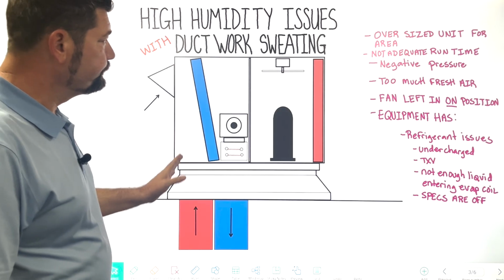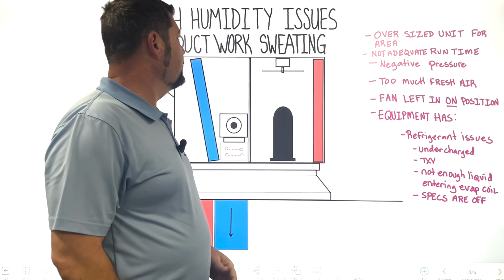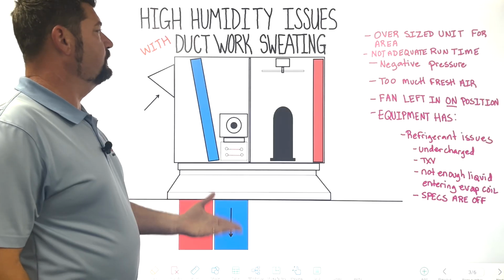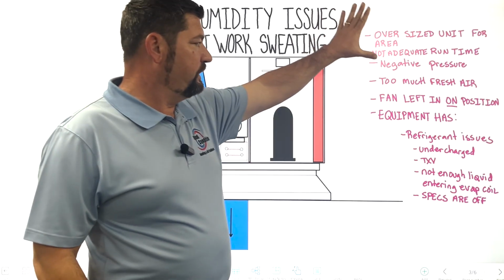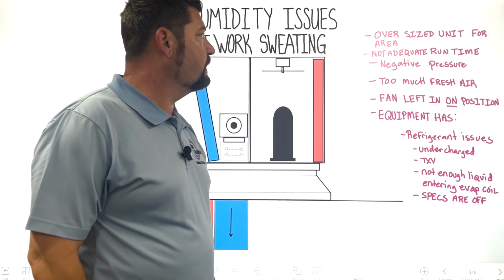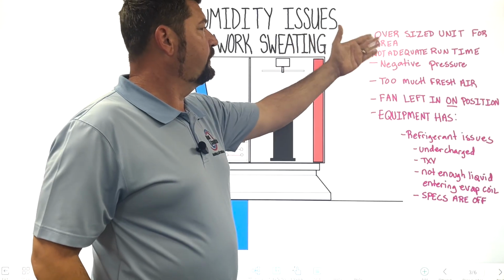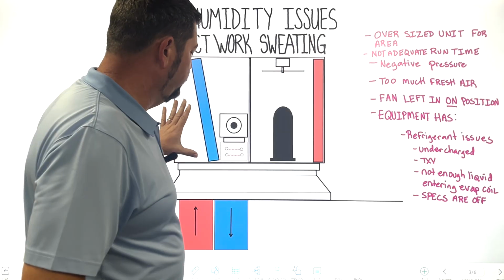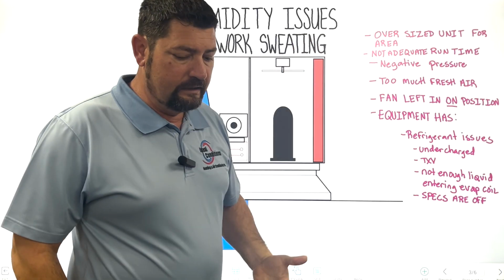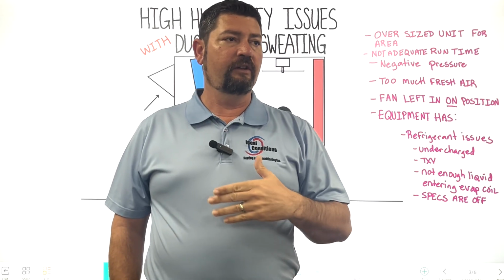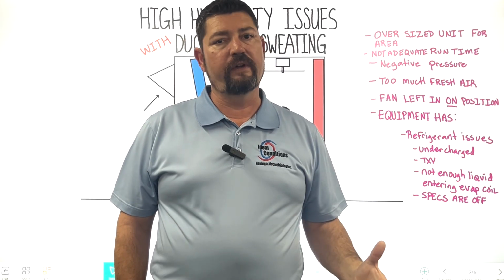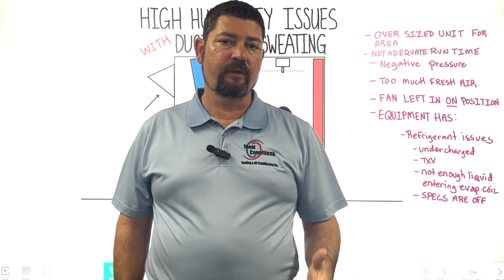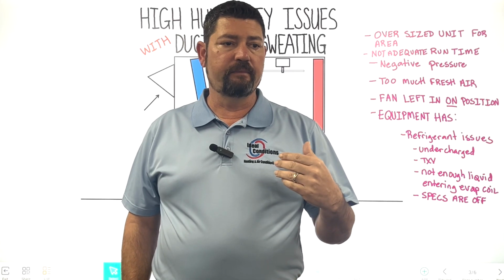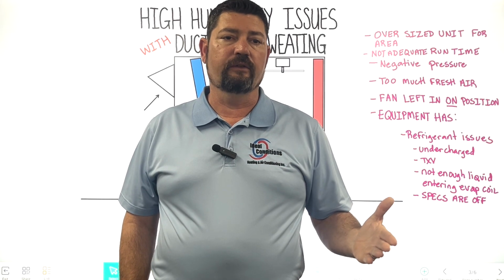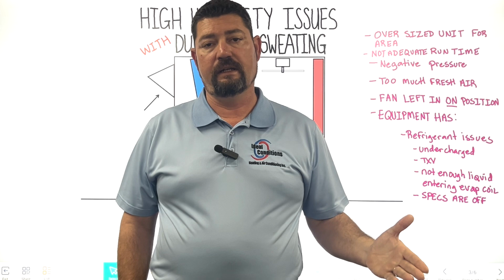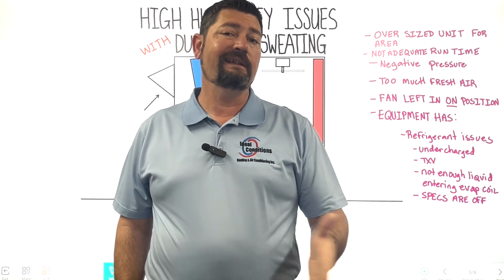All right. So what could cause high humidity? What could cause our ductwork to sweat? And I just put some key notes over here so we can stay on topic. Oversized unit for the area. So let's just say that in commercial spaces, it's very common for one tenant to move out and then walls to be put up. And when those walls are put up, the space changes. So now the demand of air has to change, but typically it doesn't.